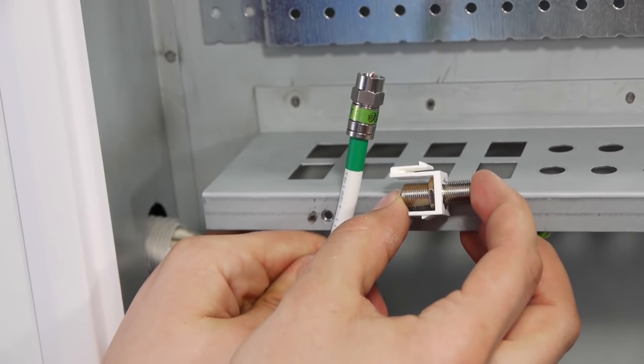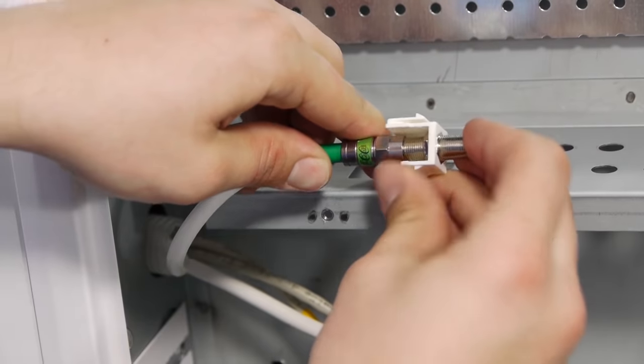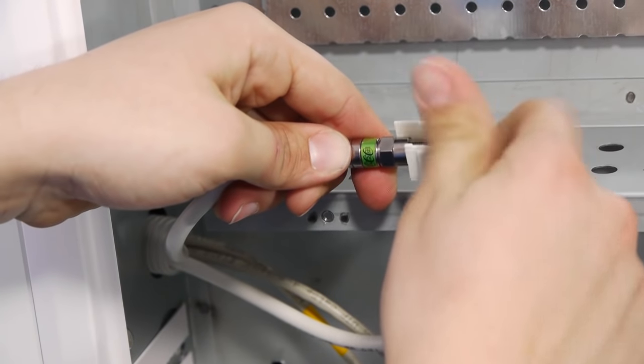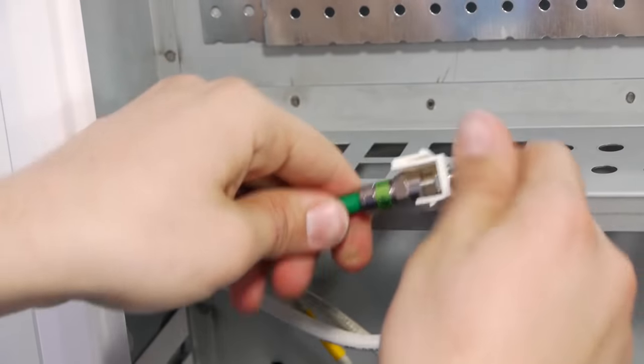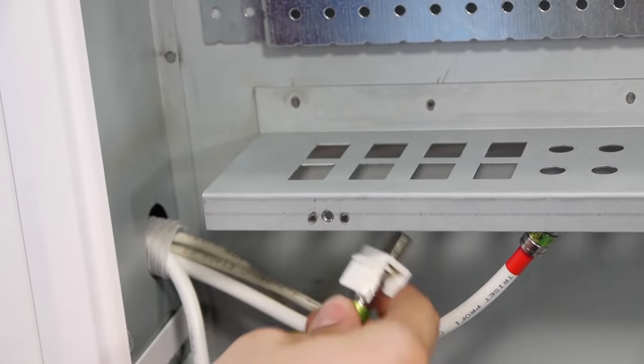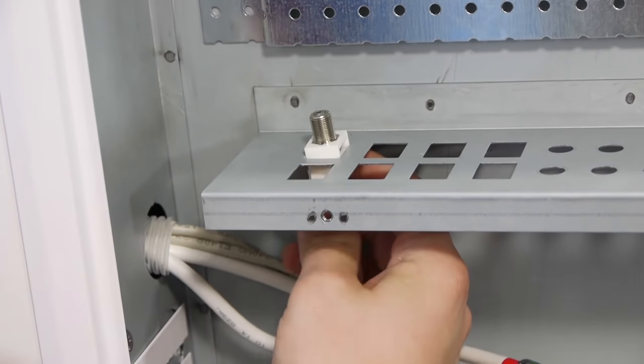The cables terminated with suitable connectors should be connected to the appropriate keystone modules that are snapped into ports of the mounting plate. It is important to keep at least the minimum bending radius of each type of cable.